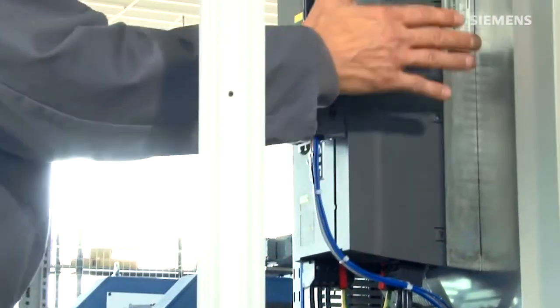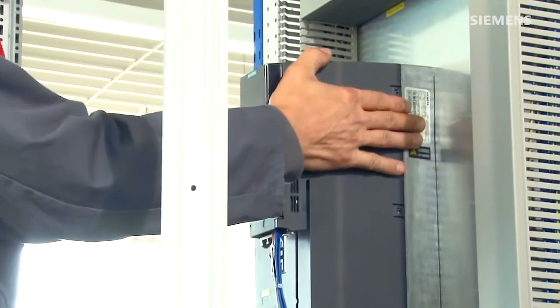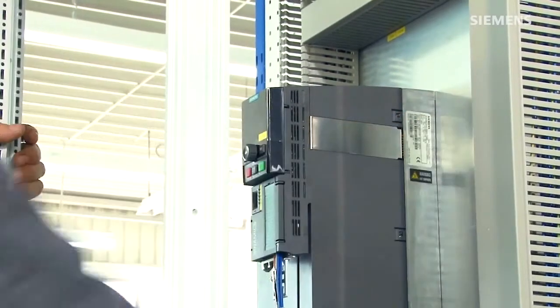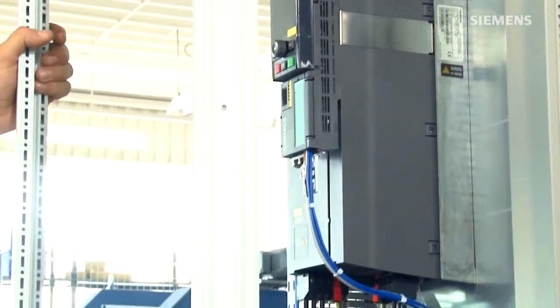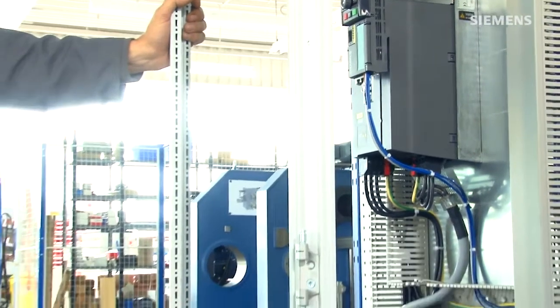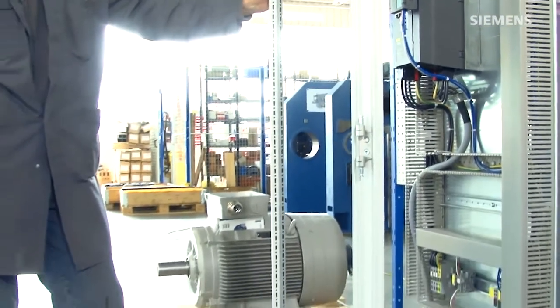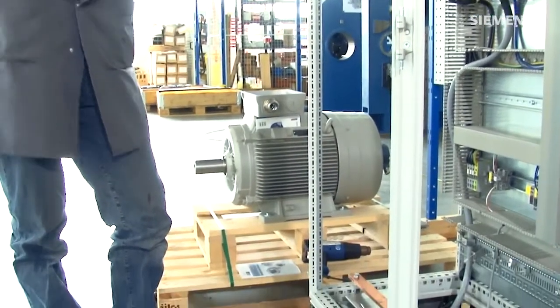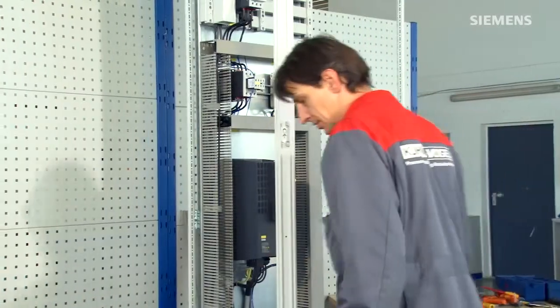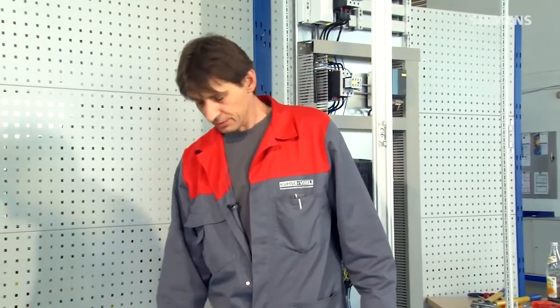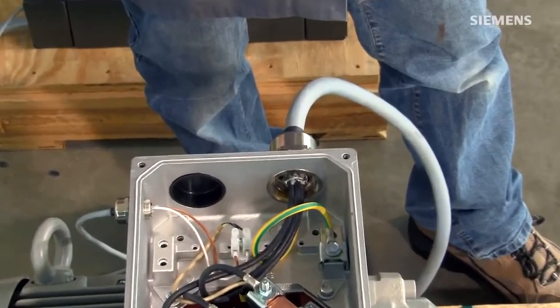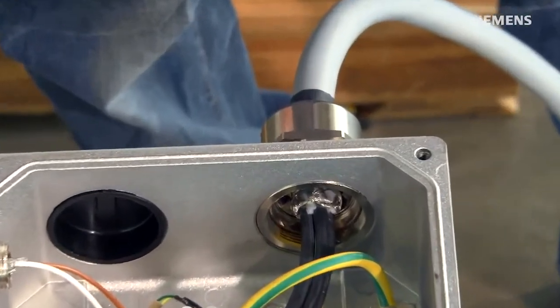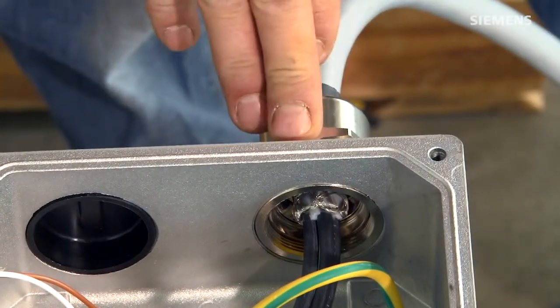Make sure that there is good contact between the frequency drive and mounting plate. It should also be noted that the connection between the drive and mounting plate covers a wide area. Do not use coated mounting plates for retrofit systems. Follow the same procedure for stripping the motor cables. It should be noted that EMC screw connections are used, which ensure an optimum connection between the shield and housing.